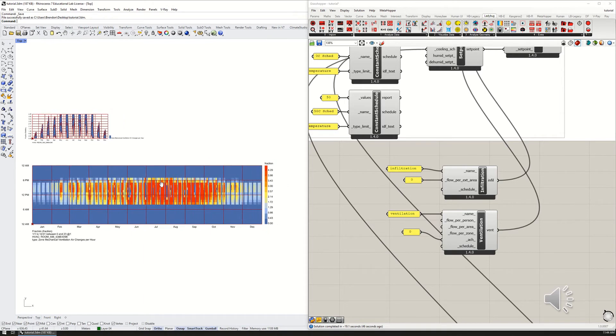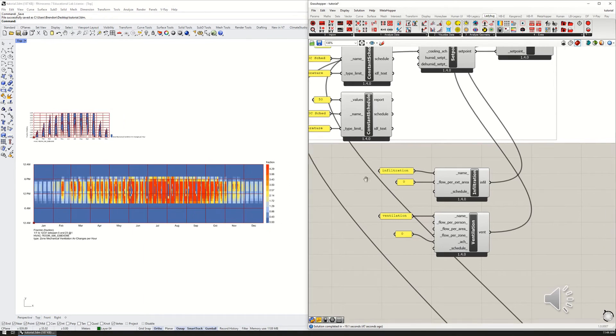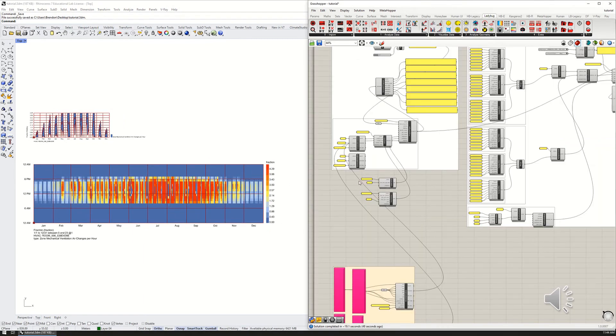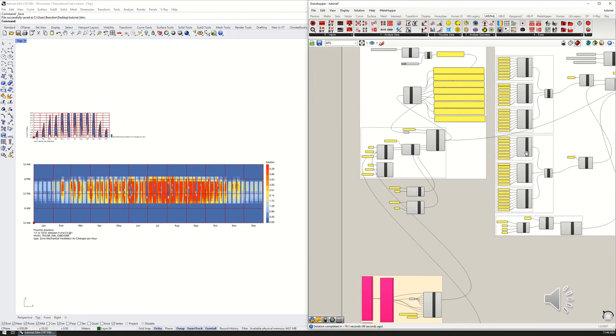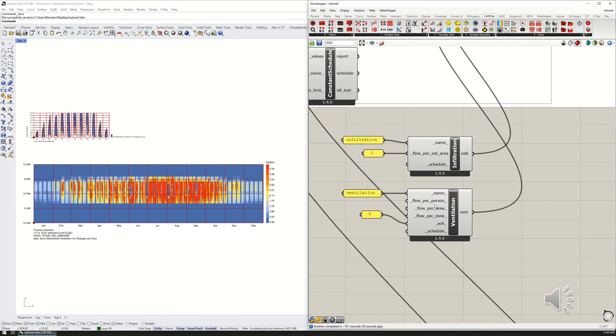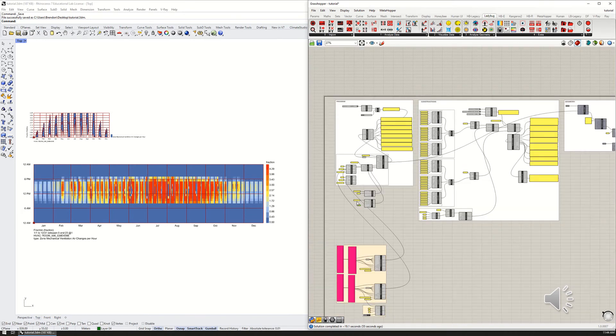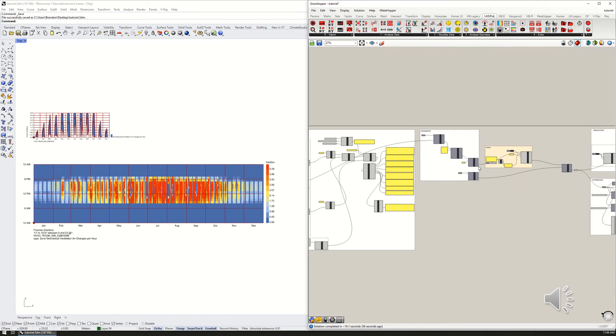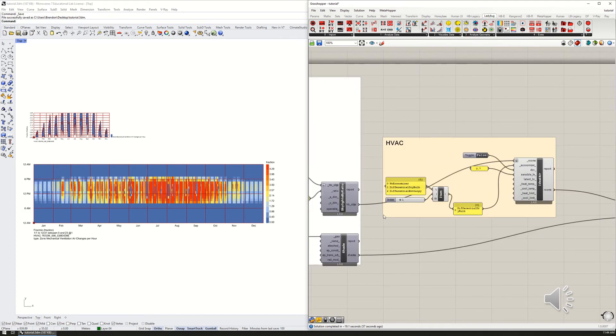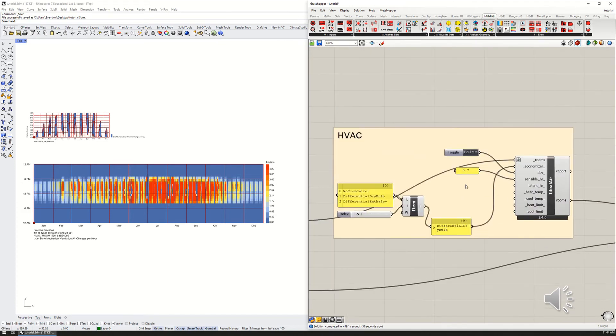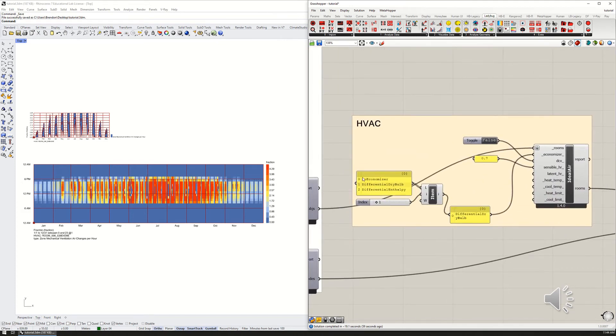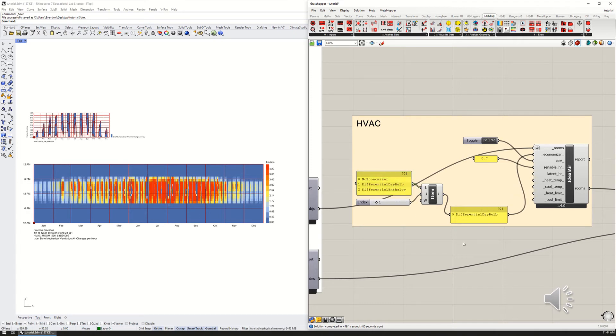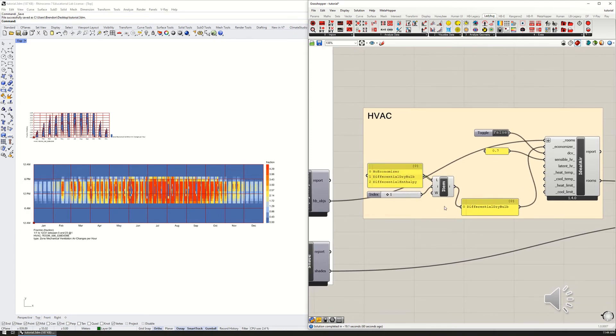Upon further inspection, what's actually happening here is our ventilation rate for fresh air is set to zero, but if you remember earlier, we set the economizer to be in differential dry bulb mode, which means that it is drawing in fresh air to cool down the zone whenever it can.